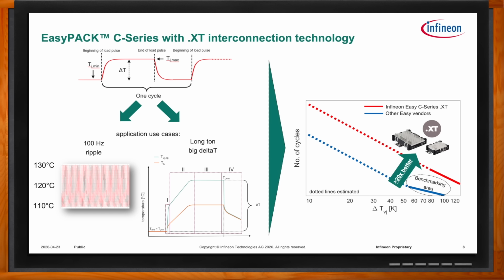Typically what we specify for our customer is shown on the right: we plot the number of cycles over different delta T's, meaning changes in temperature. By doing so, the customer is able to read out, based on the mission profile or the temperature swing, how much lifetime is consumed and how long the device would last.